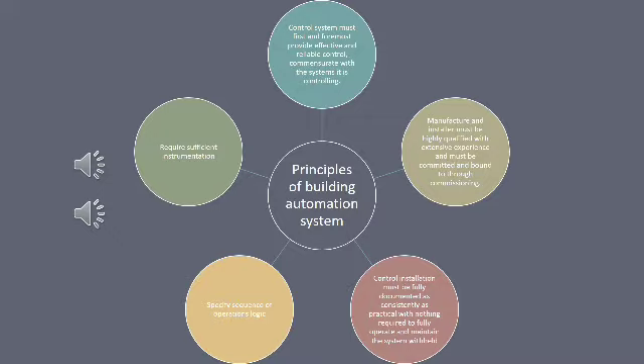This system must have principles to follow in order to standardize the procedure and the maintenance of the building, so that the contractor installing the building is aware and knows the basics of the system. The principles of building automation are: the control system must first and foremost provide effective and reliable control commensurate with the system it is controlling. The type, complexity and criticality of the system being controlled will dictate the quality and power of the control system applied in the building.